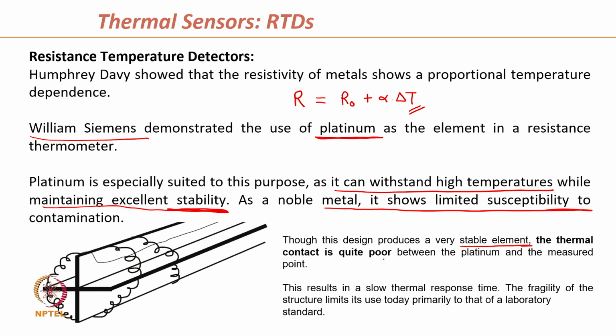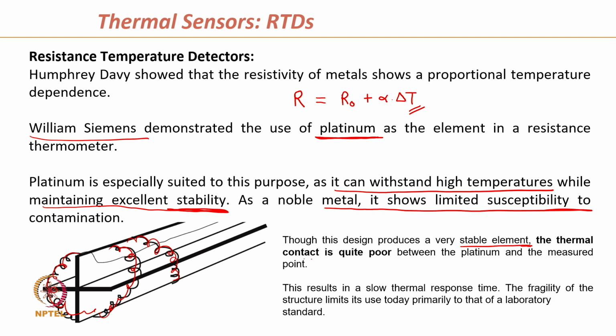So, the construction of a resistance temperature detector, or RTD, is that we take a wire of platinum and we just wind it on a glass rod or something like this. We take a glass rod and we wind a platinum wire on this rod, and this is what our RTD is. This produces a very stable element. The thermal contact is very poor.